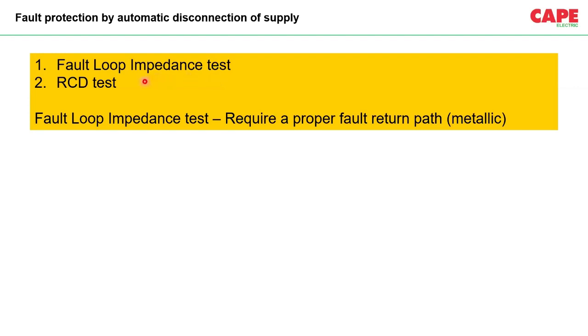Number two, RCD test. RCDs generally have a test button on the RCD. The RCD test is not about pressing the button and finding out your RCD is working. That is not it. The RCD test is carried out with an RCD tester. You have to connect the RCD tester at the output of your RCD, and this device will inject a current and find out the tripping time of your RCD. So both these tests depend upon your application. One of these tests may be required.